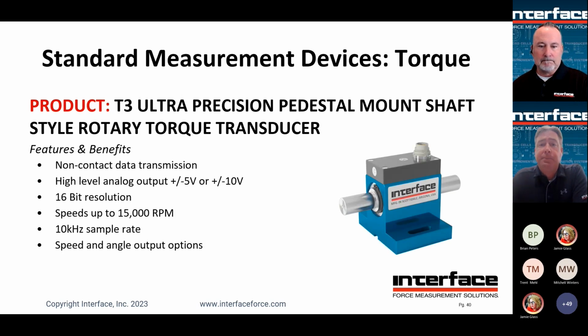Model T3, this is a pedestal mount torque transducer, with a very wide range of torques, all the way down from sub 1 Newton meter up to about 10 kilonewton meter, shaft to shaft. It's a non-contact transducer. There are no slip rings to prematurely wear. Speed rating up to 15,000 RPM, and resolution down to about 16 bits. These are also available with speed and angle optical encoders if you need to measure either angle or speed.